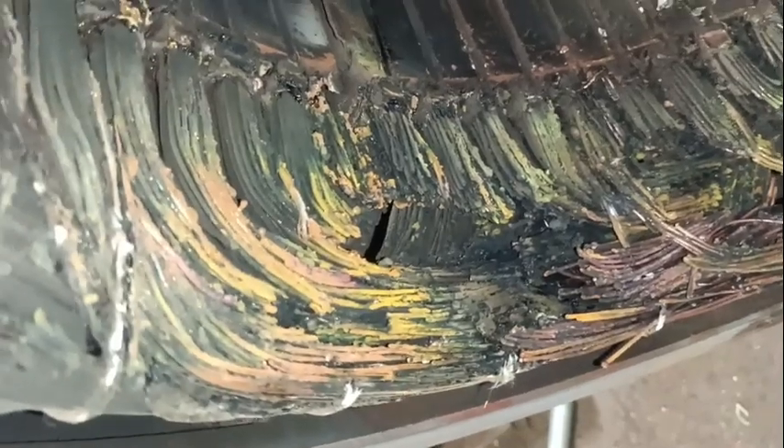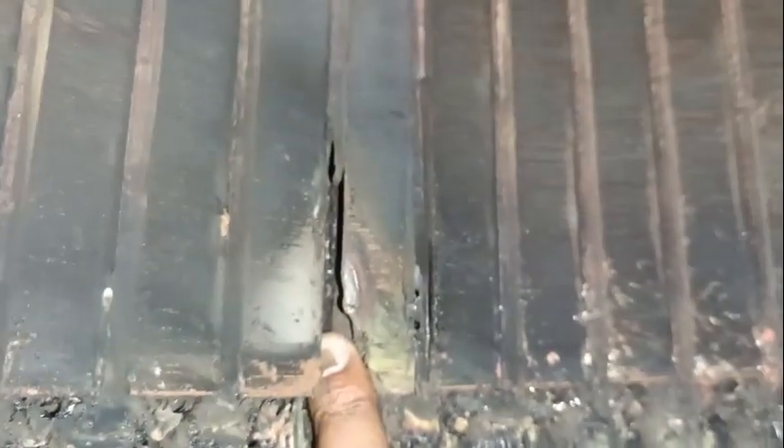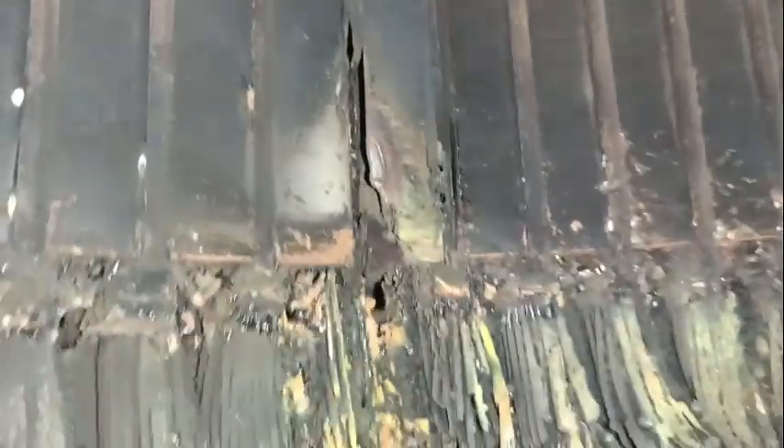In today's topic, let's look at a 750 kVA Stamford alternator which has a unique problem. As you can see, we have the main stator of this 750 kVA alternator which has winding failure on its overhang. As we closely observe the failure, we can notice that its core is also damaged. So here is our today's topic: core failure in alternator stators.